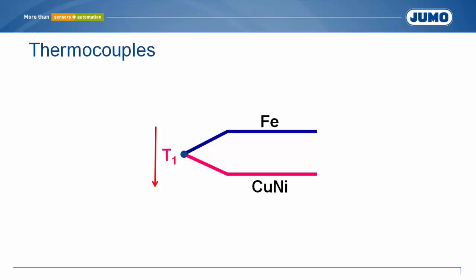The thermocouple is connected to the automation component at the terminal point. Due to the material transitions, two thermoelectric voltages result. The sum of the partial voltages is a measure of the temperature T2 present at the terminal point. The field device measures a voltage proportional to the difference of T1 minus T2. For this reason, the terminal temperature T2 must be measured and added to the measured value.